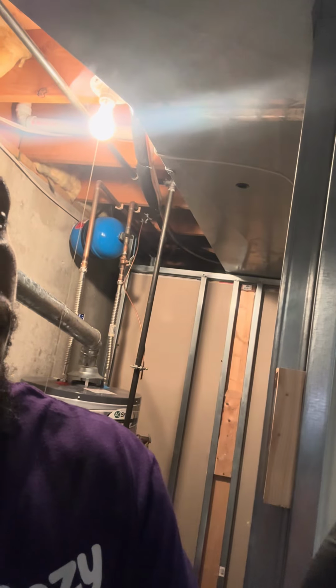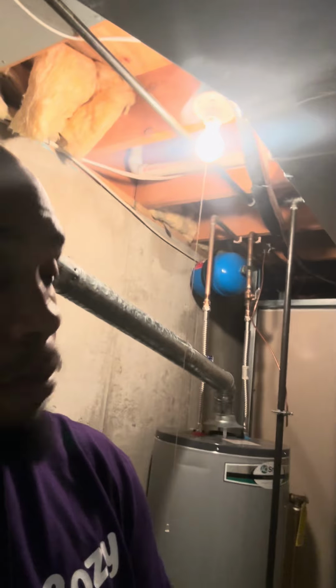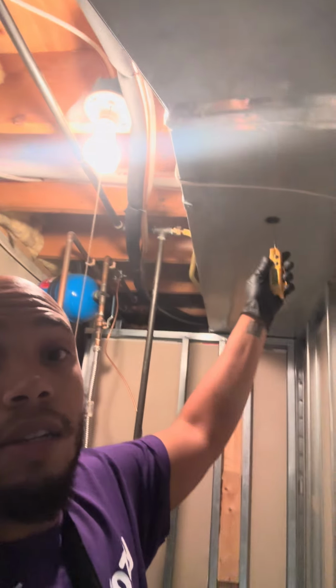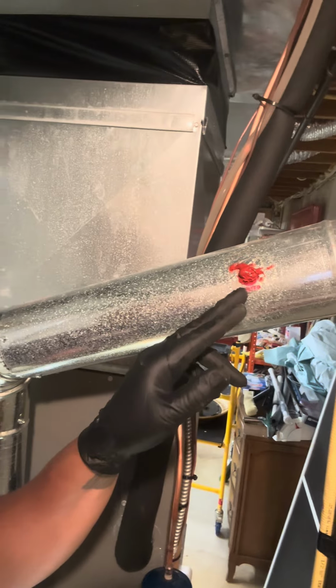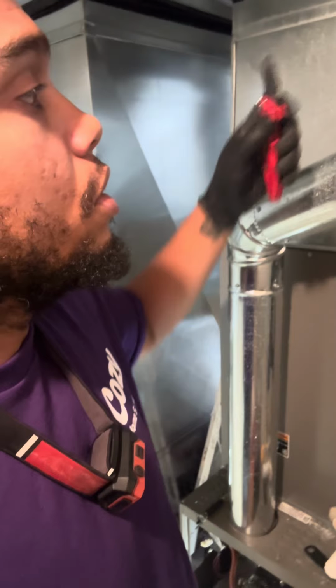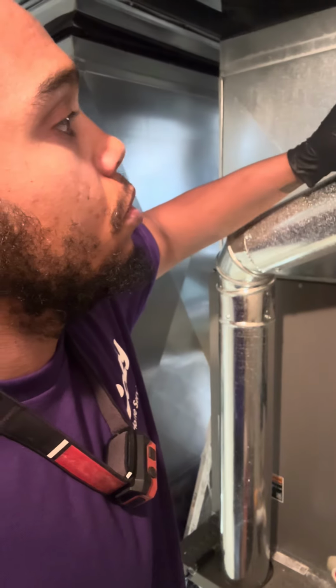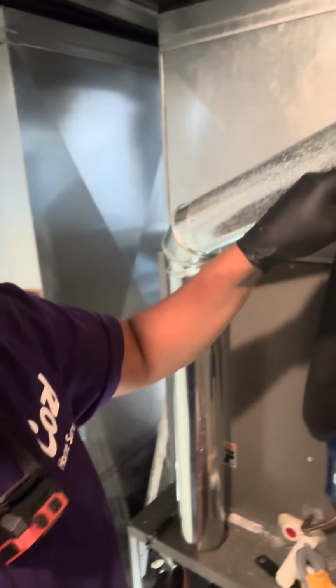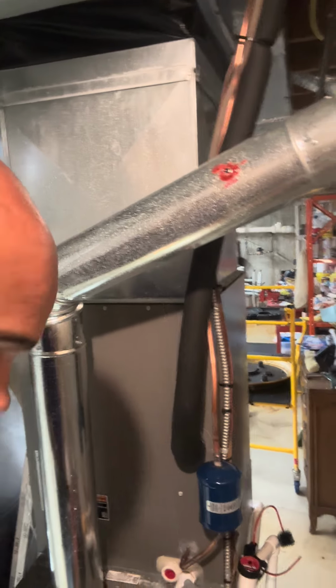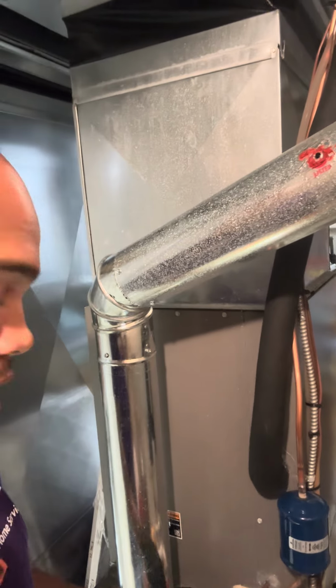So I need to know my return air. So I have one temperature sensor that I'm gonna be placing in the return duct. I have another temperature sensor that I'm going to be placing in the supply duct. Most furnaces will already have a hole right here that lets you know that another technician was here already and did a combustion test. That other technician was me. I've been here for the last few years. This is just high temp silicone. You can just pull it off. And then there's your test hole right there. So I'm gonna go ahead and get my analyzer and put that in there.